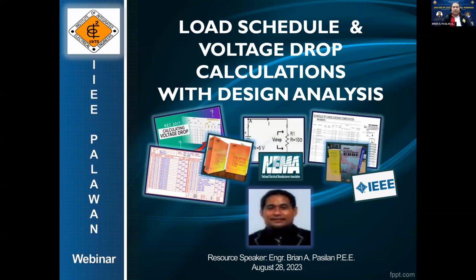Kasi yung load schedule natin, the purpose of which is in sizing up our conductors, our protection devices, and yung voltage drop din is also one of the elements in sizing up our branch circuit conductors and feeder conductors.